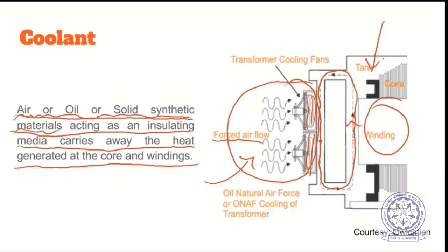And if the oil inside is circulated using a pump, then again that is forced cooling. Or you can leave it to a natural process, by which hot oil will go upwards, and then since the temperature outside the transformer is low, it will cool and then come down like this. If it happens through a natural process, then that is natural cooling.